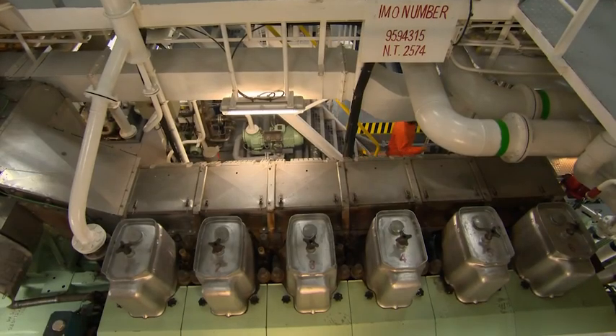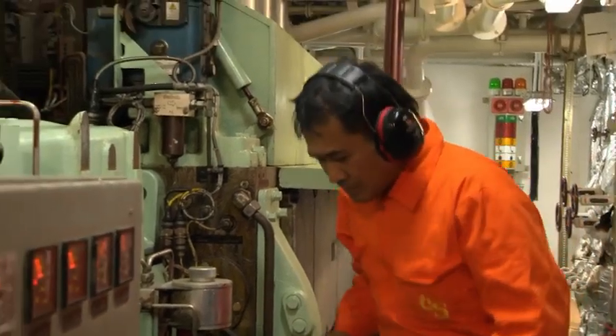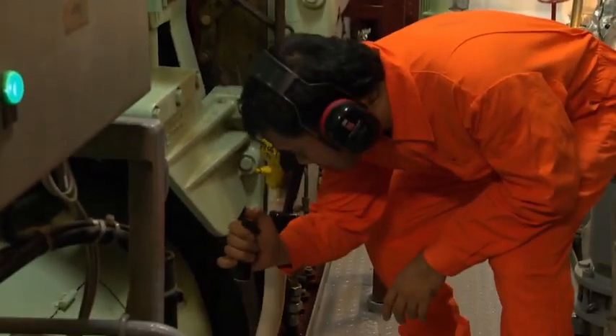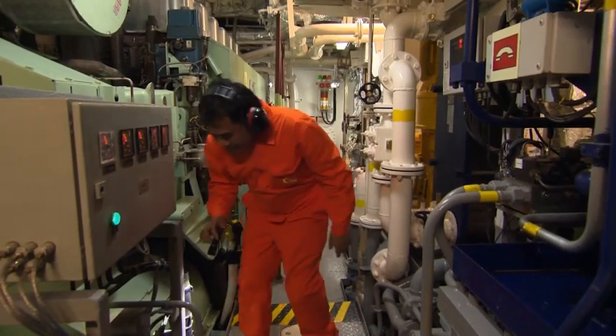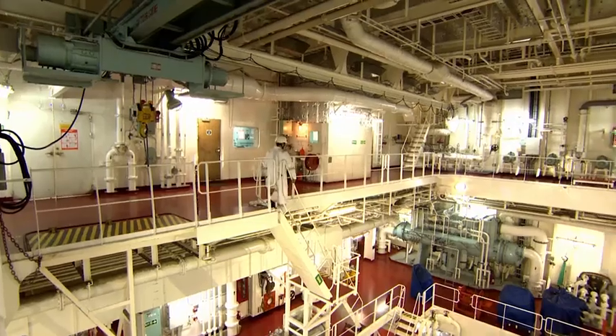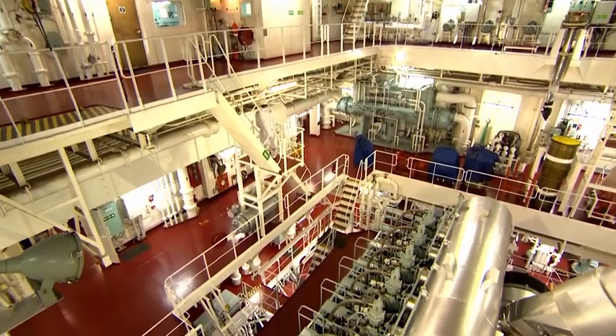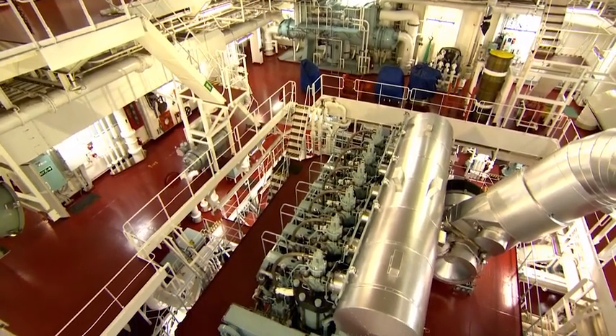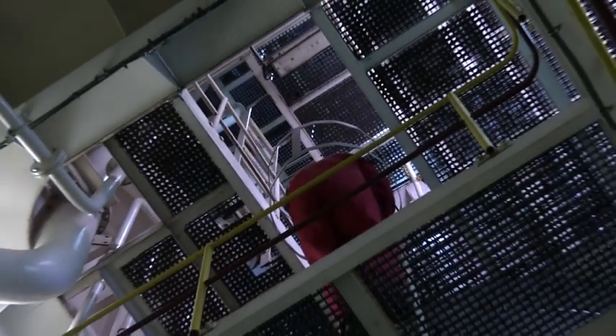There are a number of different types of machinery space fire. The most common of these is fires caused by oil leakages, which account for more than half of all machinery space fires. Scavenge fires, if large enough, are particularly prone to extending through hotspots on the scavenge trunk. There are also crankcase explosions and fires involving the funnel, uptake, economizer or superheater.